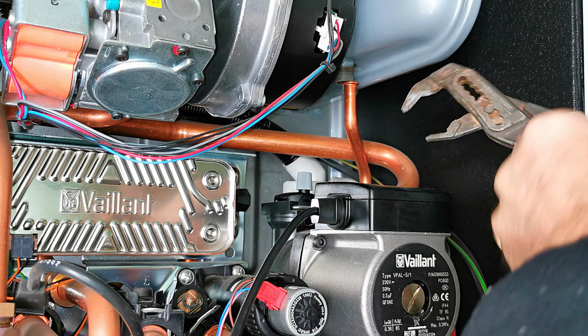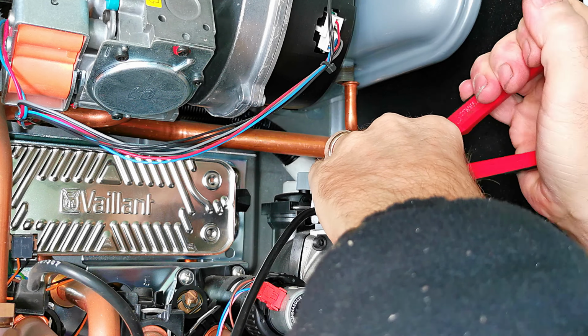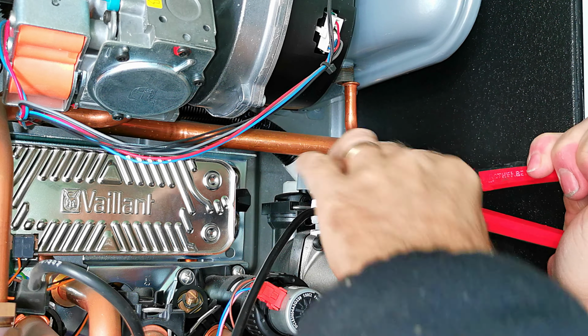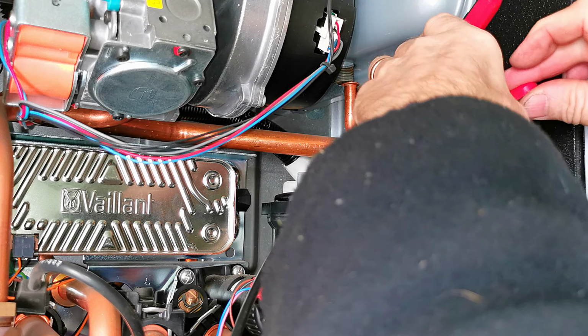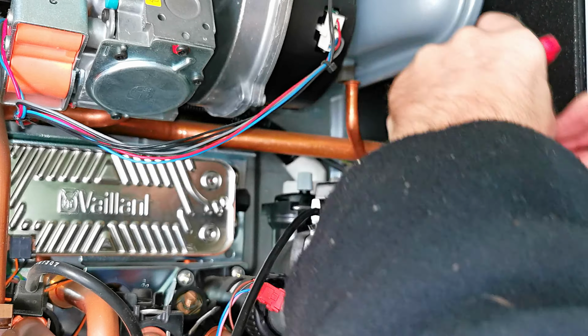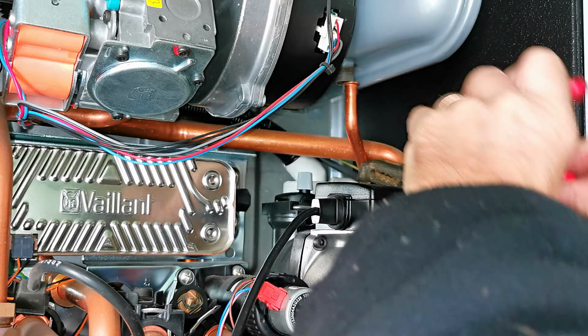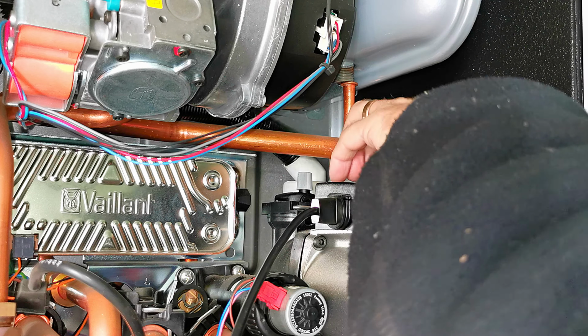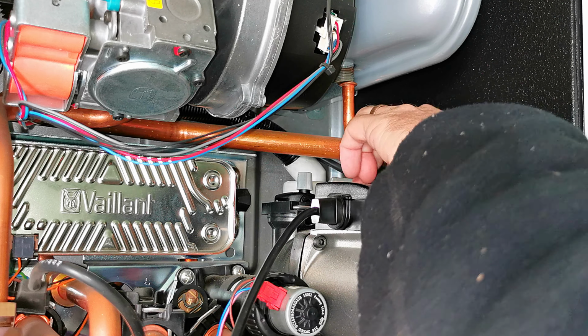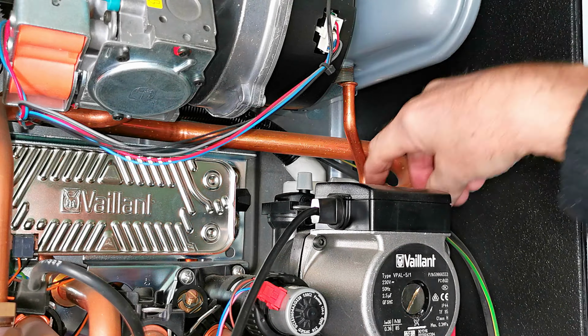I'm then going to use a pair of grips to undo the nut which is on that return pipe. Now this nut shouldn't be very tight because it's done up onto a plastic fitting, and also when I refit it I need to be really careful that I don't over tighten it because again it's going onto a plastic fitting. And there we go, that's now undone and removed.